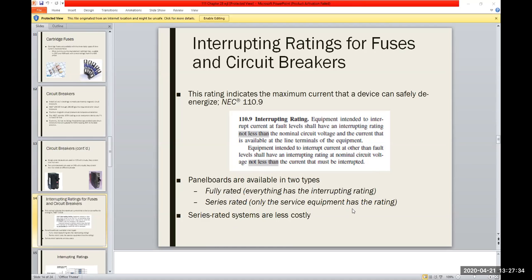So service equipment, depending on the ratings that you have on it, could be series rated, right? And that will depend on what kind of panel board you're allowed to use. And then fully rated, where everything has the interrupt rating listed. The series rated systems are less costly. The fully rated one, of course, is ready for just about everything. And really, you have to apply it to your situation. It would depend on what kind of home and home wiring you're going to have, and what kind of appliances are going to be run through the house, and that kind of thing.